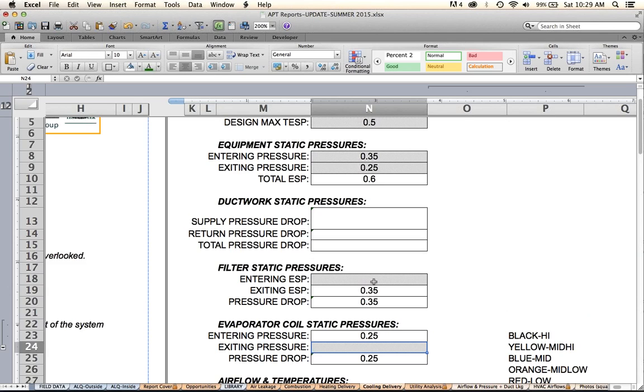We're going to take one on the exiting side of the filter. We're going to take one before the AC coil, and we're going to take one after the AC coil. And those are our four readings, and they're going to populate a whole bunch of stuff for us. So before the filter, and now, if you can imagine here, the entering pressure on my equipment is 0.35. I'm going to say the entering pressure on my filter is 0.15. And then past the coil, it was 0.25. I'm going to say it's 0.10.